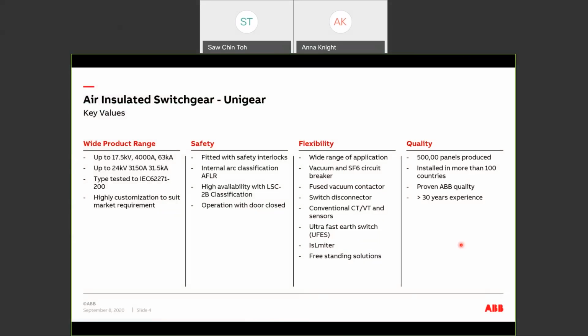So what should we consider when selecting the medium voltage switchgear? First, we need to consider the uniformity on site. Meaning, can we use the same product for different applications or voltage rating at site? So UniGear ZS1 can support up to 17.5 kV, 4000 amp, and 63 kA. And for 24 kV, it can support up to 3150 amps and 31.5 kA.